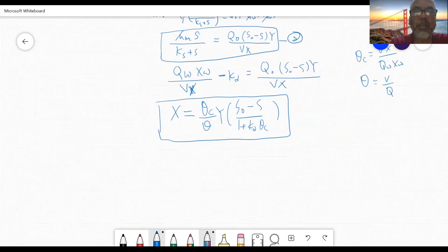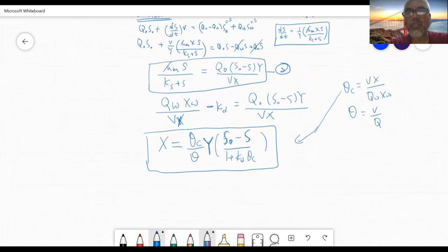In this equation, Y is a yield coefficient, S naught is substrate concentration in influent, S is substrate concentration in the aeration tank, theta c is the sludge retention time, theta is hydraulic retention time, and Kd is the decay coefficient. So we can compute the concentration of biomass in aeration tank if we know theta c, the sludge retention time, the hydraulic retention time, if we select a constant yield coefficient and decay coefficient, and if we know the concentration of substrate in influent and effluent.